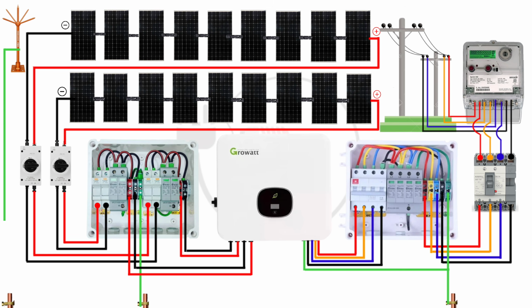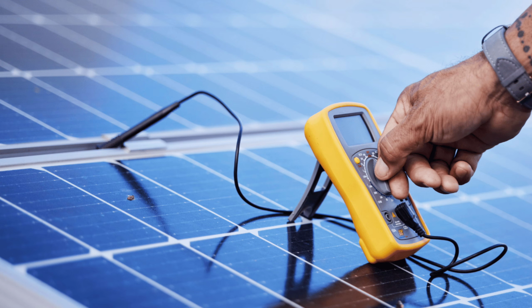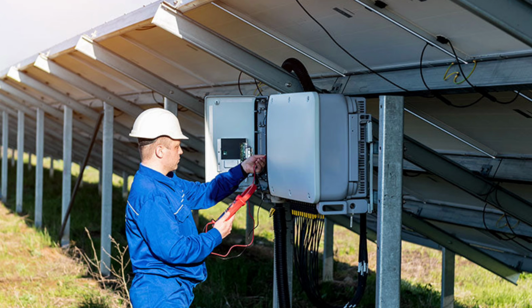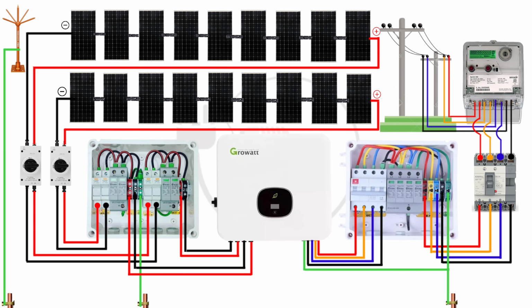lightning strikes. Remember, each of these connections must be made securely and according to all local electrical codes. Use appropriate size cables and ensure all connections are tightened and correct. After the connections are made, test the system and verify the voltage at various points. Check the operation and ensure the inverter is functioning correctly. And that's it. You have now successfully connected your 10 kW AC side grid tie solar system.